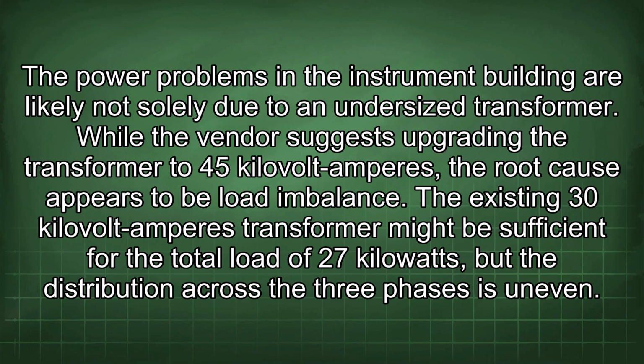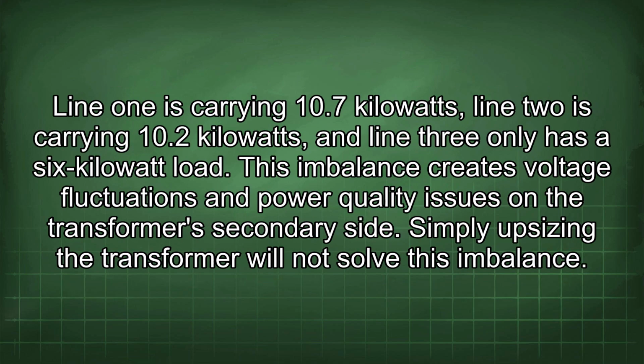Power problems in the instrument building are likely not solely due to an undersized transformer. While the vendor suggests upgrading the transformer to 45 kVA, the root cause appears to be load imbalance. The existing 30 kVA transformer might be sufficient for the total load of 27 kW, but the distribution across the three phases is uneven. Line 1 is carrying 10.7 kW, line 2 is carrying 10.2 kW, and line 3 only has a 6 kW load.